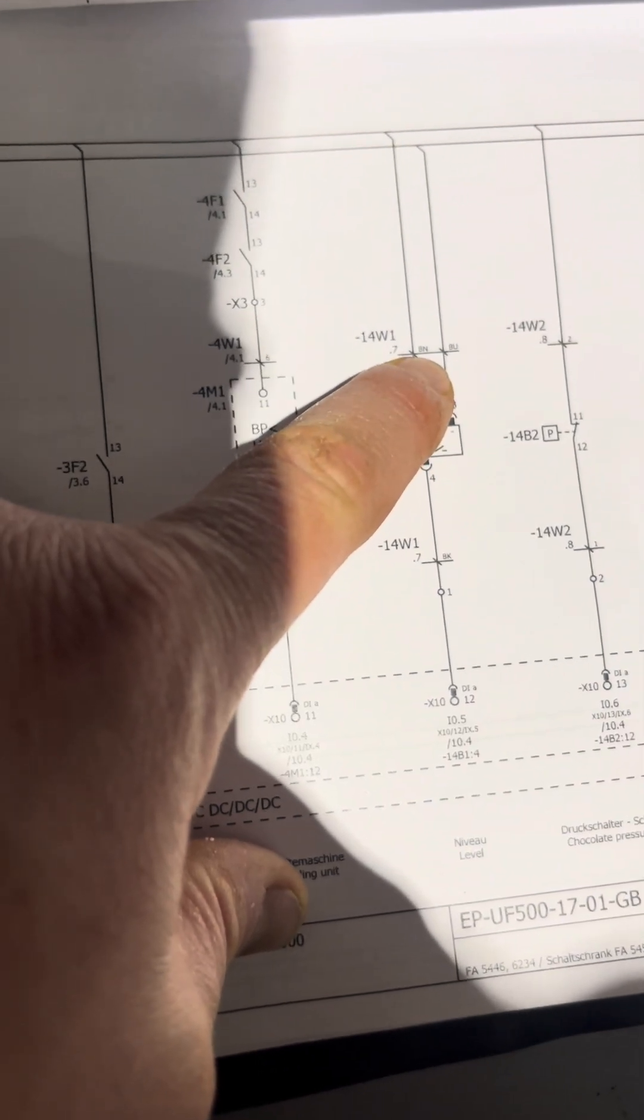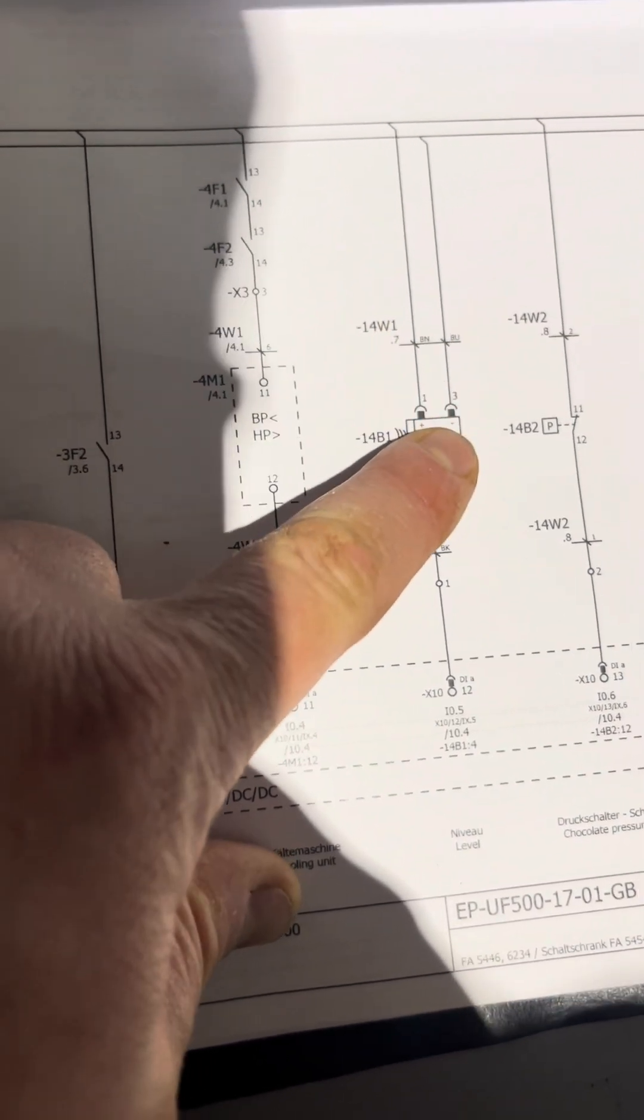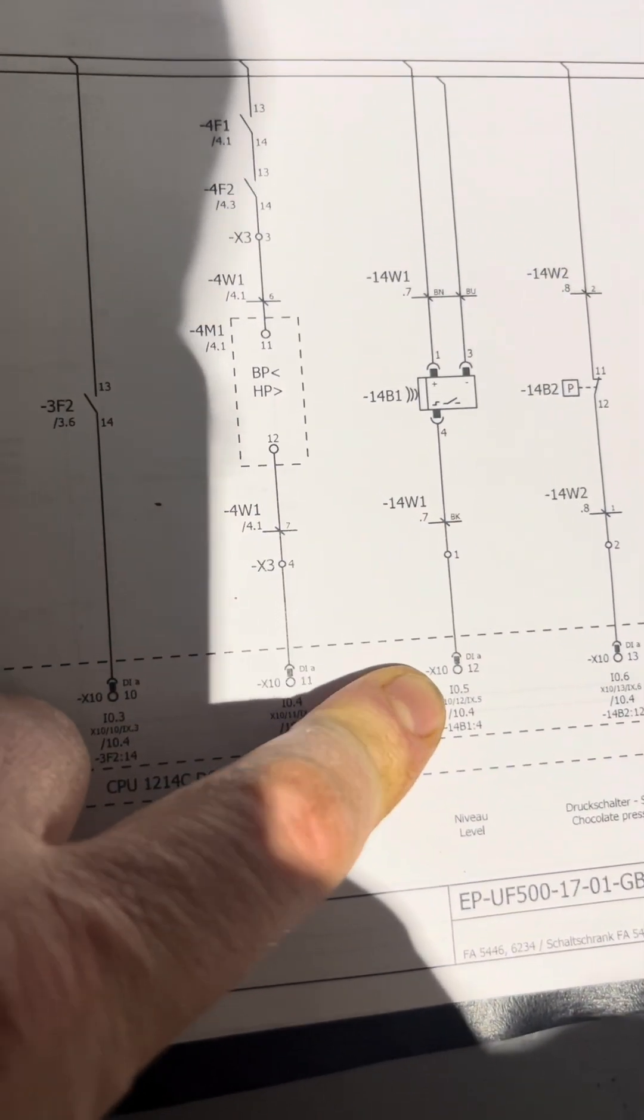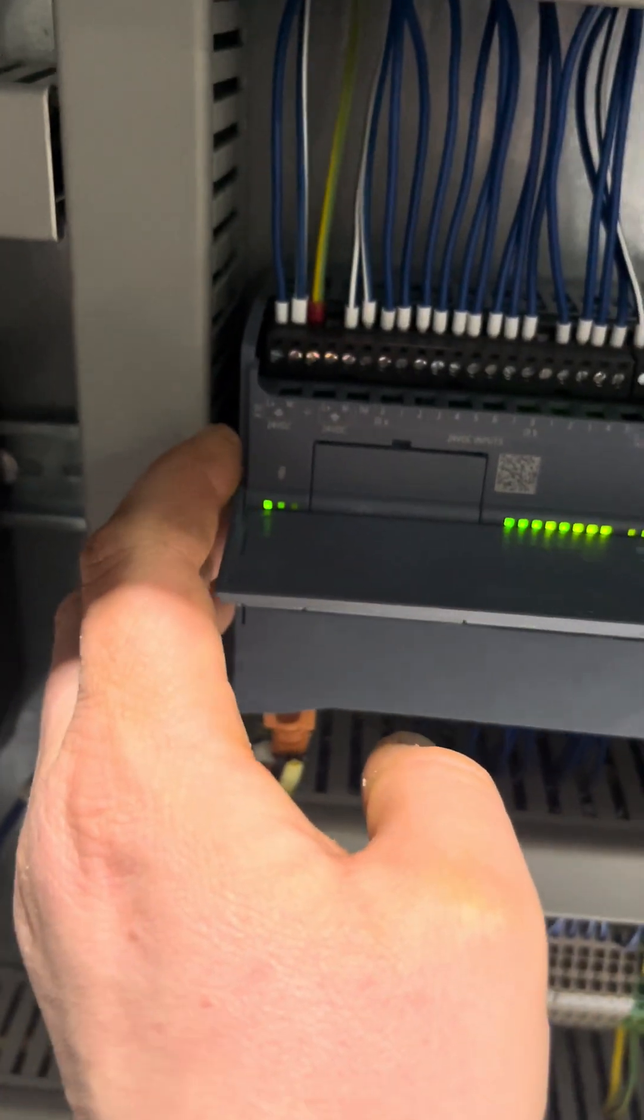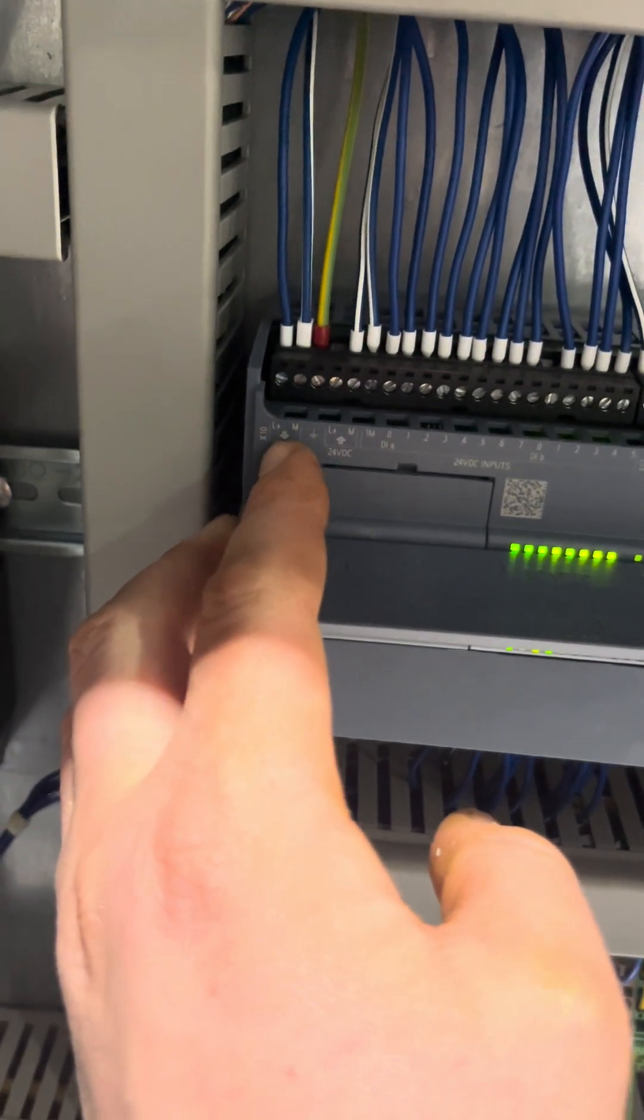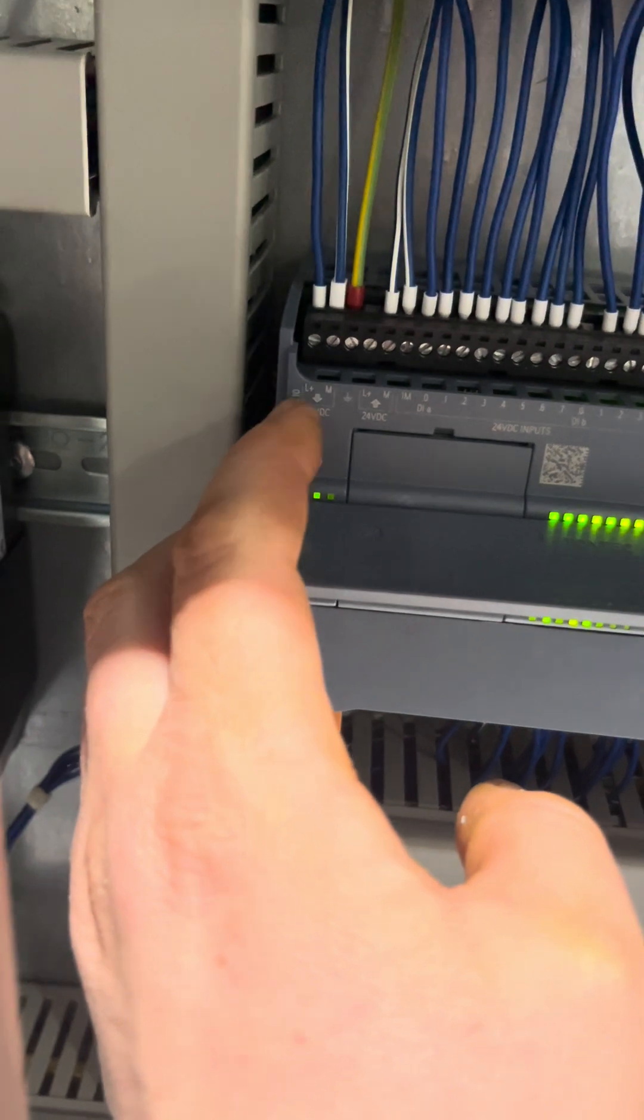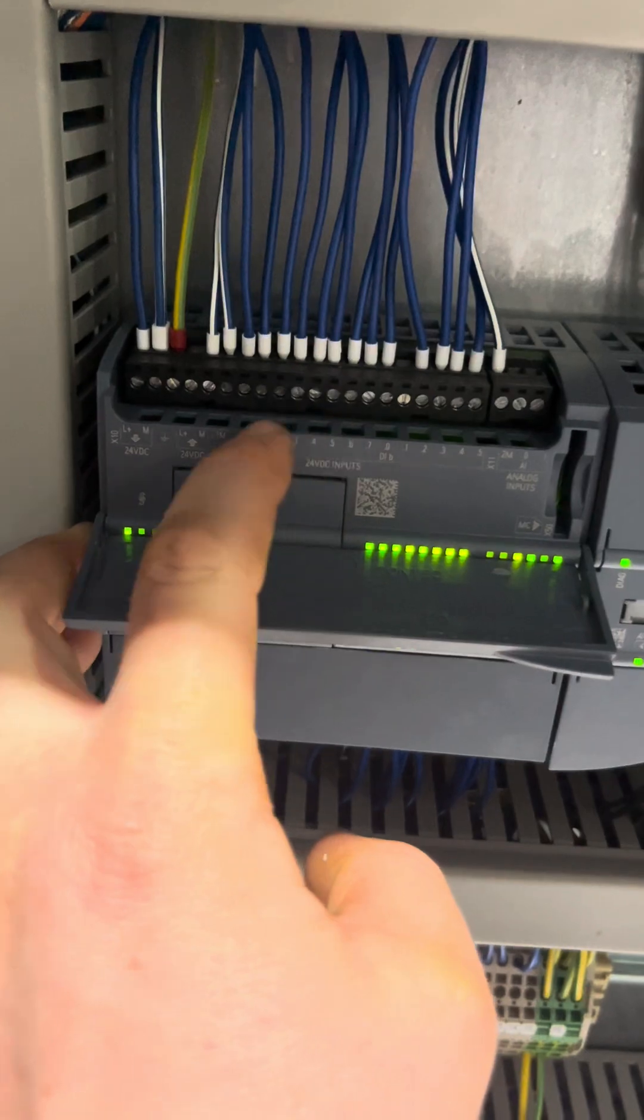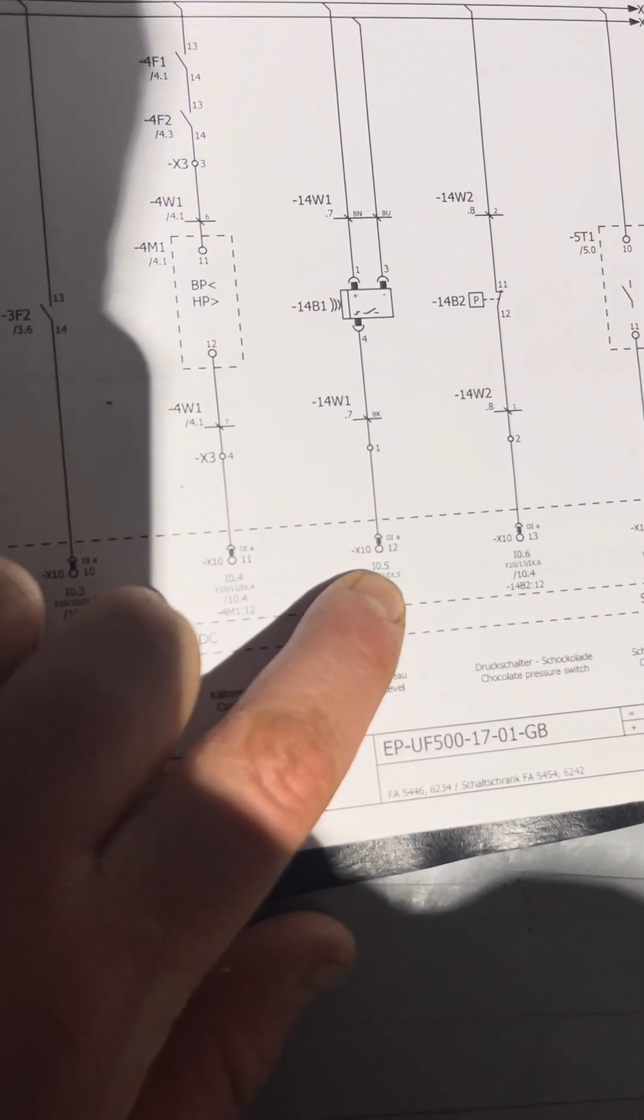And as you can see, we've got our 24 volts coming in on the blue and the brown, and then we've got a black switch cable coming out. And that shows us what terminal that goes into the PLC. So I drop the cover down. As you can see, we've got our 24 volt, that's what powers the PLC itself. And then alongside that is the input's voltage going out to the inputs, the 24 volts, and then your negative. And there's your terminals for all of the inputs. So what we can do is we're going to look for what number it is. And on the schematic, it's shown as X10. So we're going to look back up make sure we've got X10, so we know what we're looking at.